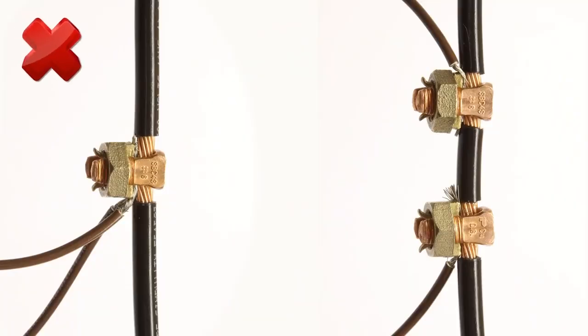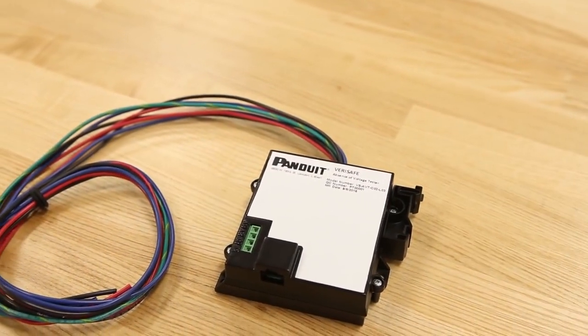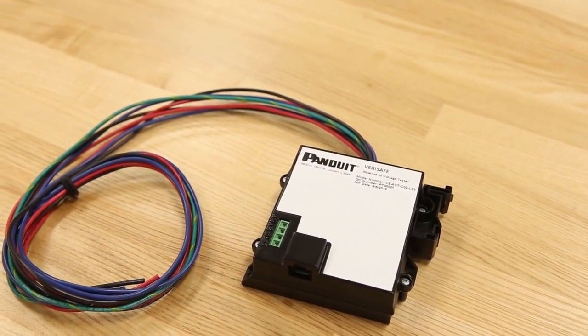It is important that the sensor leads are not mechanically connected to each other. This ensures the integrity of the test the tester function and installation test. There are also two ground leads that must be mechanically separated.